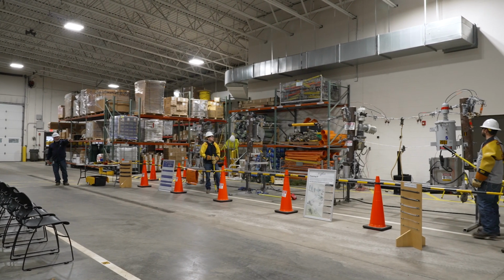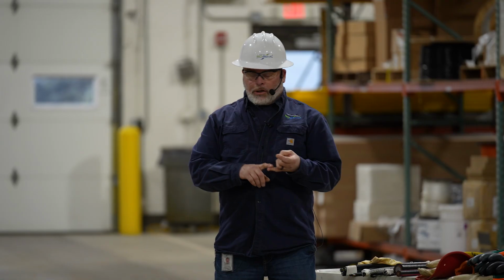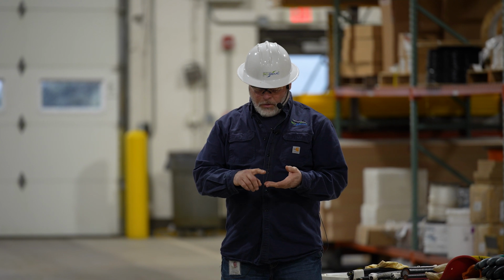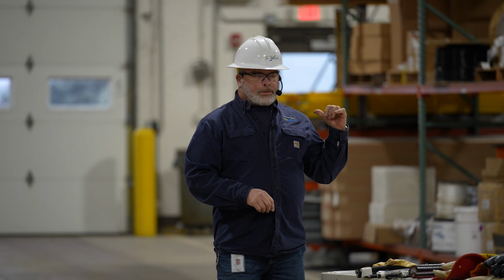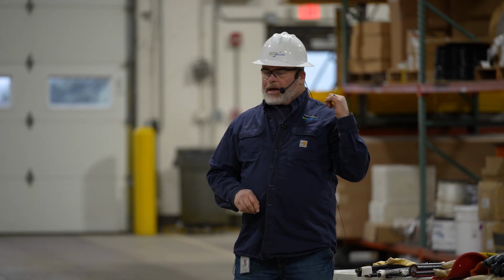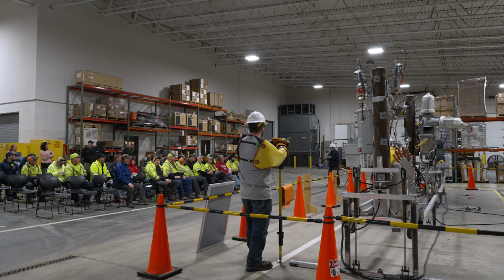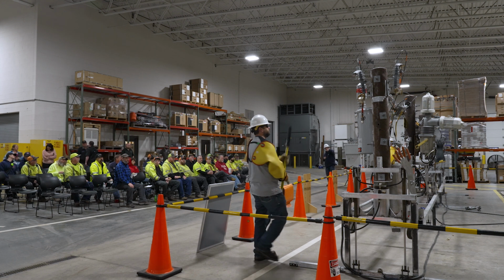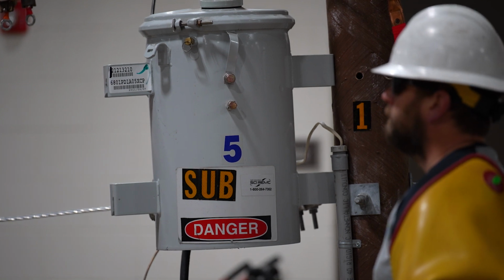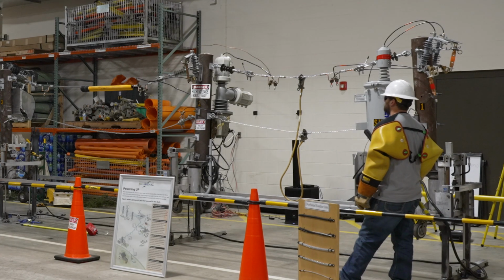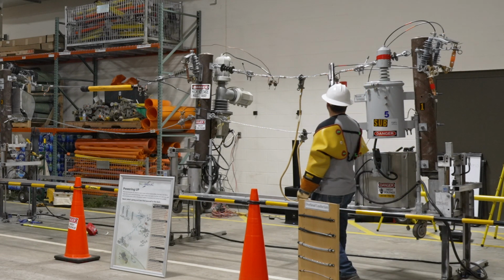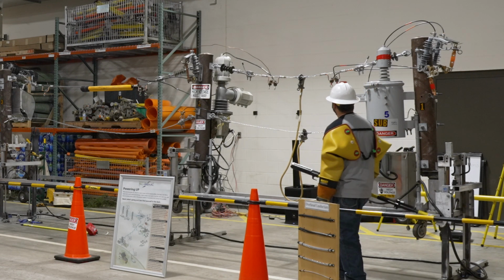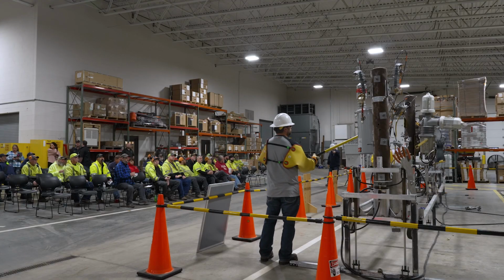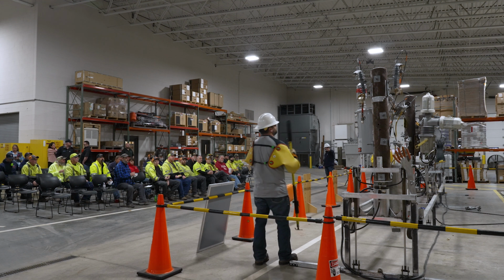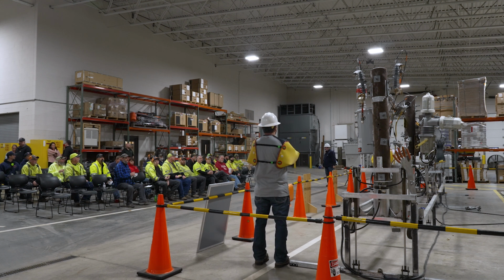So electricity is generated at a generating plant, whether it's coal, natural gas, wind, solar, hydro, or nuclear. Our generator outside is actually acting as our generating plant. It's putting out 240 volts, and we come into this transformer at the end where it's labeled substation. These transformers are actually "stupid." You can send 7,200 volts in the top, and it'll transform the voltage to 120/240 coming out the bottom, or like we're doing, we're putting 120/240 in the bottom, and it's coming out 7,200 at the top.